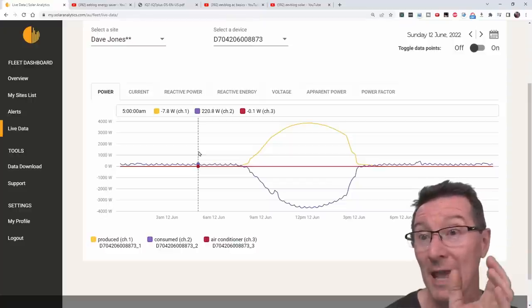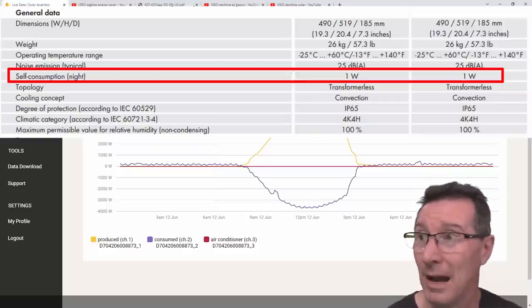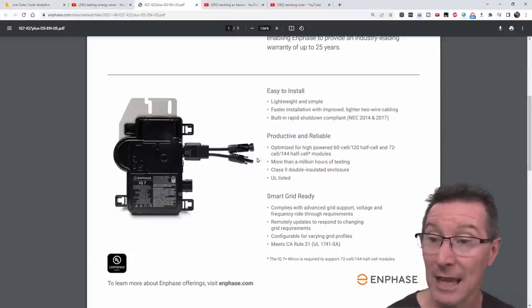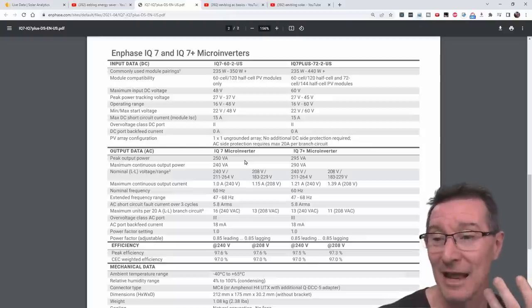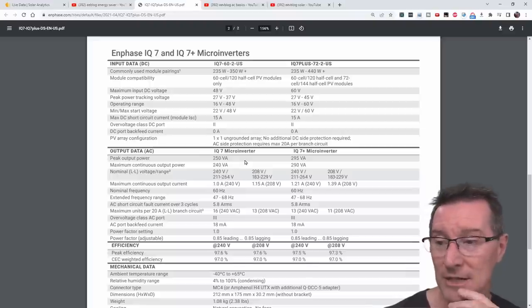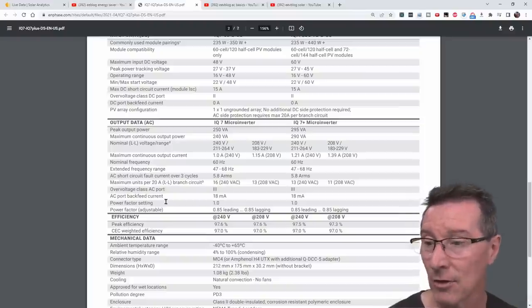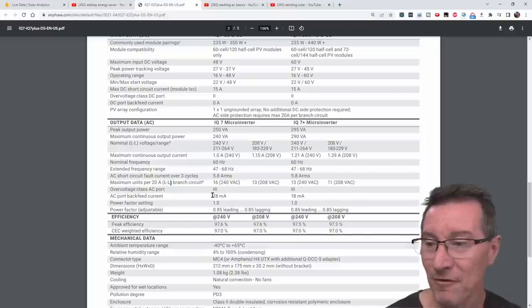Interestingly, Enphase does not tell you anywhere on the datasheet, anywhere on the website — and I've talked to them about it — they do not mention the standby power. They mention the standby power of the Envoy system, which they say is 5 watts, but they don't say the VA — the apparent power — for it. We'll go into the architecture of this later in the video. The Enphase inverters have active power factor correction, so when generating it'll be a power factor of 1.0, adjustable from 0.85.